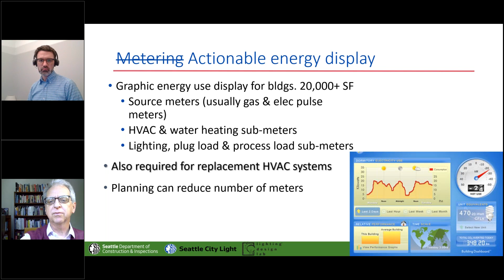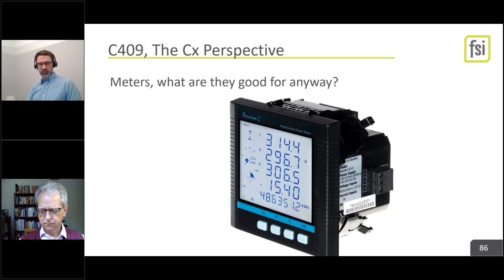Yeah, for HVAC equipment you're replacing above certain size capacities. From a commissioning standpoint, these meters are golden—they give us so much more data about how the system is performing seasonally than just reading a trend log to see if you're meeting the set point. They're fantastic for that, and fantastic for owners to know long-term whether they got what they paid for.